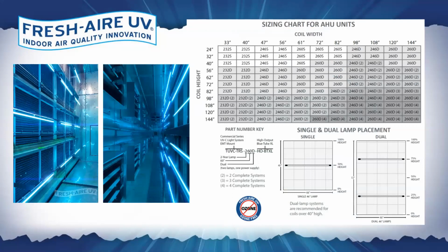Sizing is really simple, as I gave you a little idea there. For sizing, it's one lamp every 30 to 40 inches for coil disinfection. And if we want to really allow for higher level air disinfection, we would put one lamp every 10 to 15 inches. And we do have a very easy matrix cross-reference guide in order to size. You just line up the width and height of the coil, and it'll tell you how many lamps are required and what length lamps you will need.